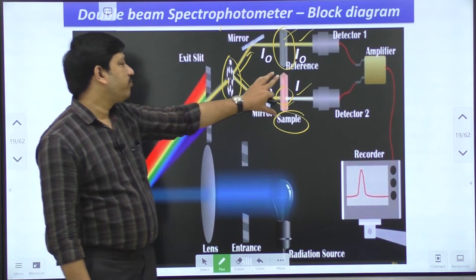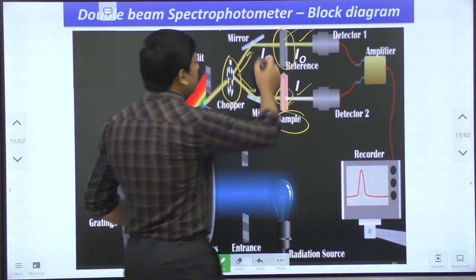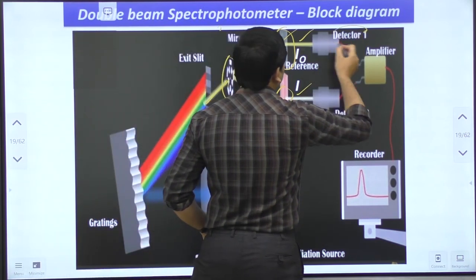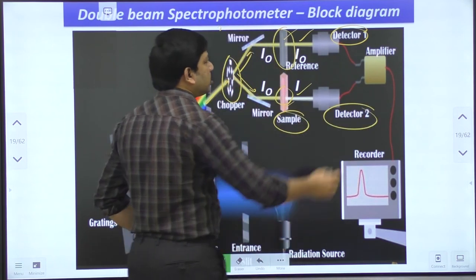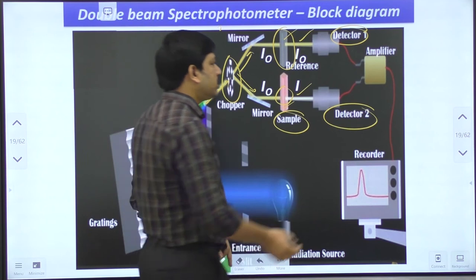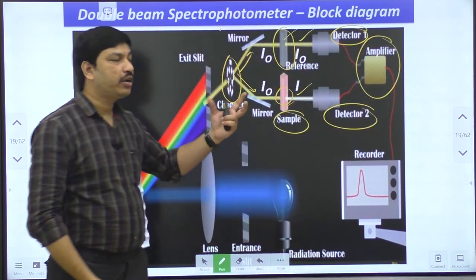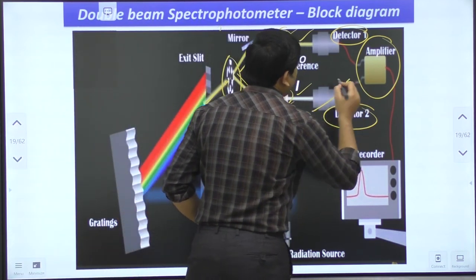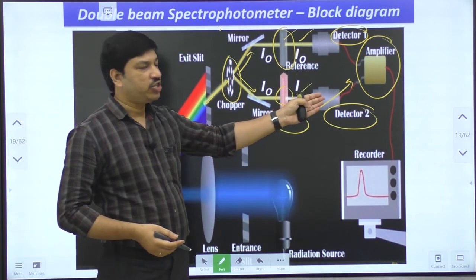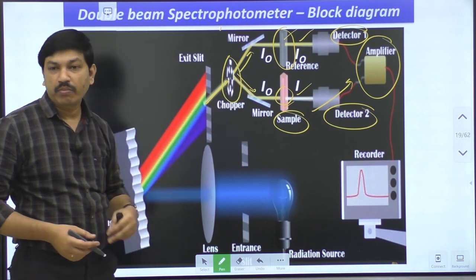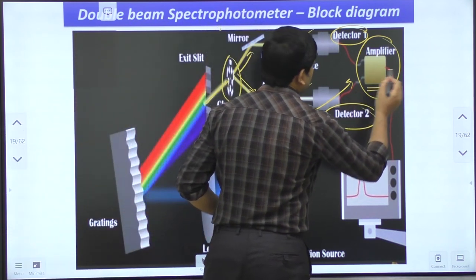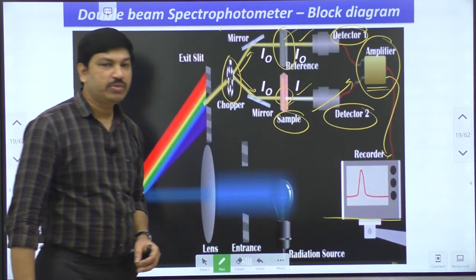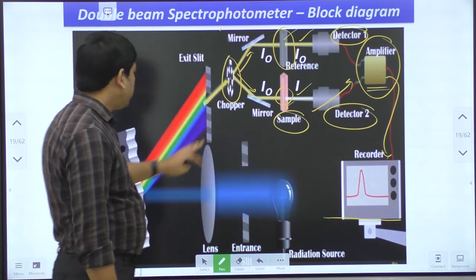Both the sample and reference produce transmitted radiation after absorbing their respective amounts from the incident radiation. Detector one and detector two each collect the transmitted signals and send them to the amplifier. The amplifier collects signals from both the reference compound and the unknown compound. The unknown sample shows a large difference in radiation intensity, while the reference shows little change. All these differences are detected by the amplifier, which then produces an absorption spectrum as output.